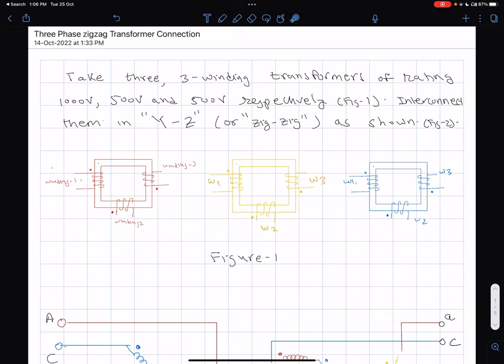The second reason is more practical: the zigzag connection is actually used in practice. It's not a routinely used three-phase connection, but it is used to provide phase shifts similar to what you see in a star-delta transformer, or some other value of phase angle shift, and to achieve objectives like providing a grounding neutral.